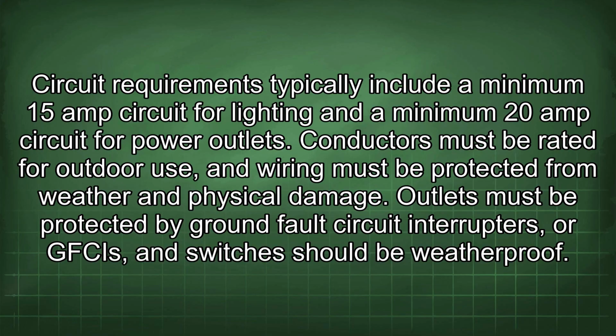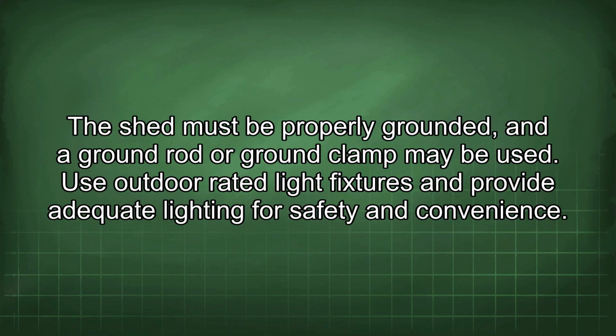Conductors must be rated for outdoor use, and wiring must be protected from weather and physical damage. Outlets must be protected by ground fault circuit interrupters, or GFCIs, and switches should be weatherproof. The shed must be properly grounded, and a ground rod or ground clamp may be used. Use outdoor rated light fixtures and provide adequate lighting for safety and convenience.